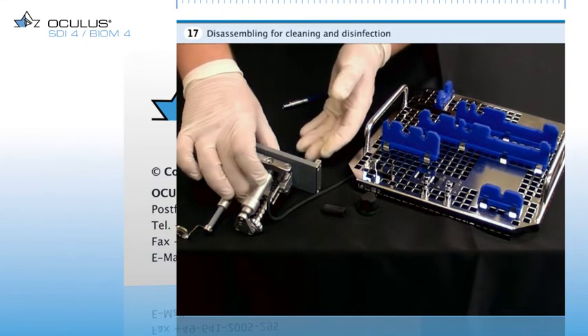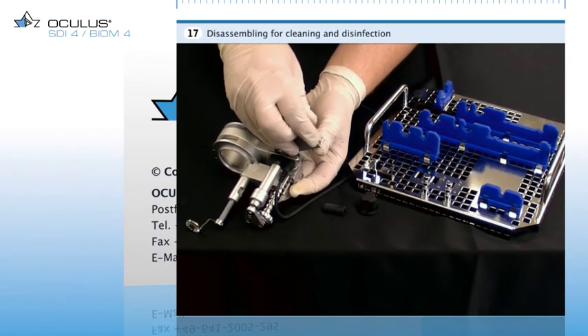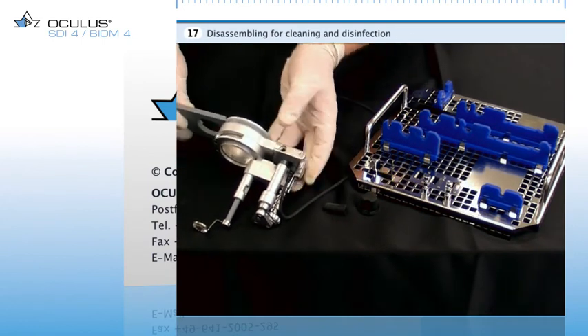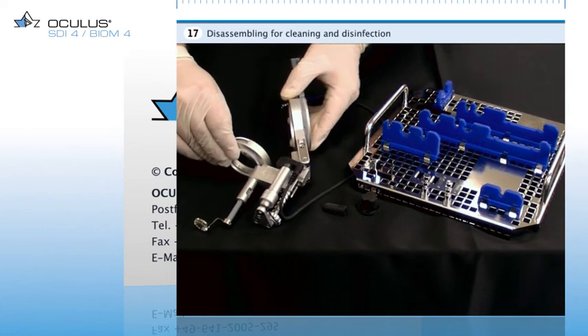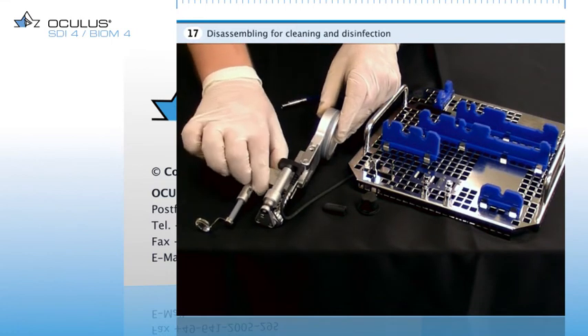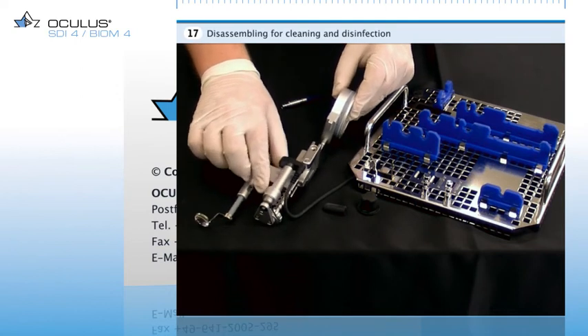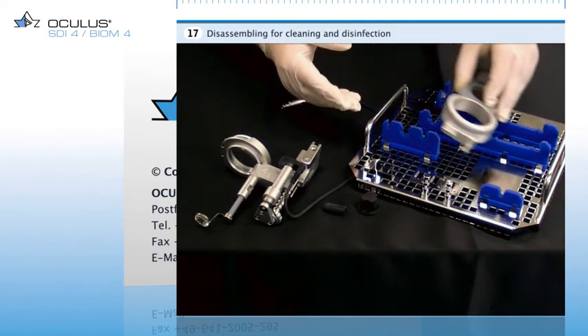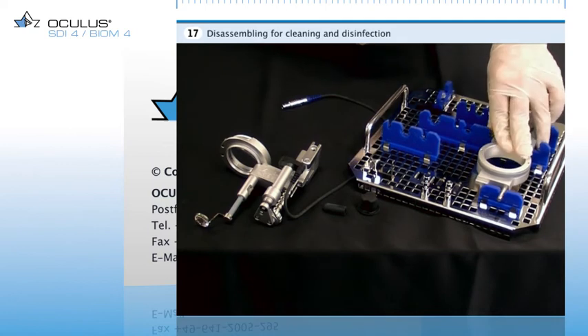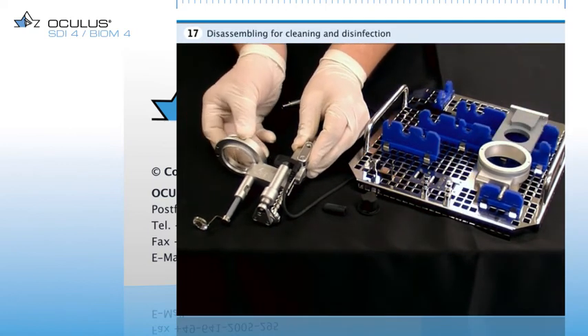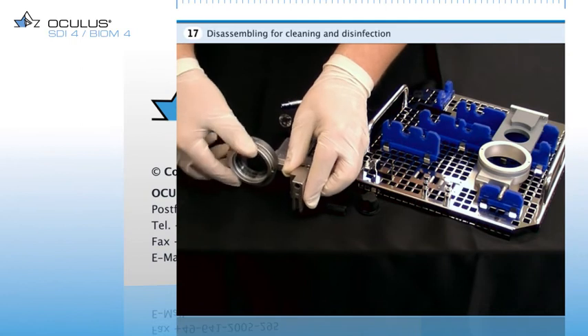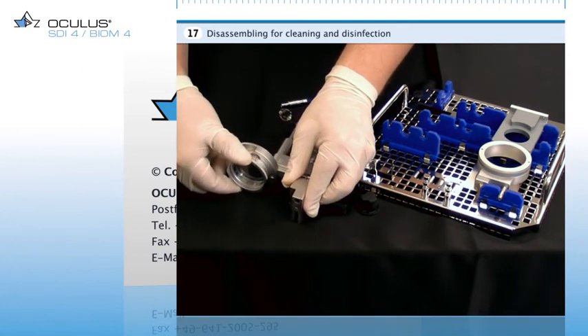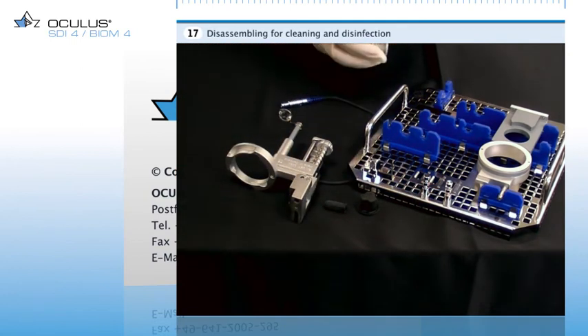For disassembling the BIOM, do the following. Swing out the adapter by 90 degrees and then remove it from the BIOM. Place the adapter plate on the sterilization tray as indicated by the lasered-in instructions. Release the reduction lens by turning it counterclockwise in the lens holder. Place the lens on its designated mount on the sterilization tray.